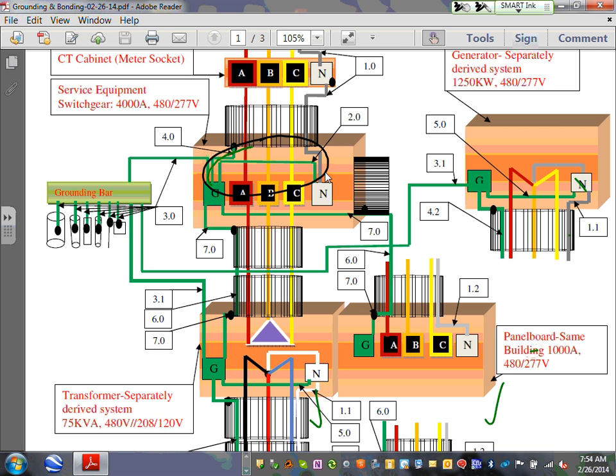That conductor is number 2. This is called main bonding jumper. So Karen, what you do with the main bonding jumper, you take the neutral and you bond it to the ground. You bond the neutral to the ground and to the enclosure inside the switchgear. That's a code requirement. Can I have a thumbs up, Chad? We know what a main bonding jumper is.